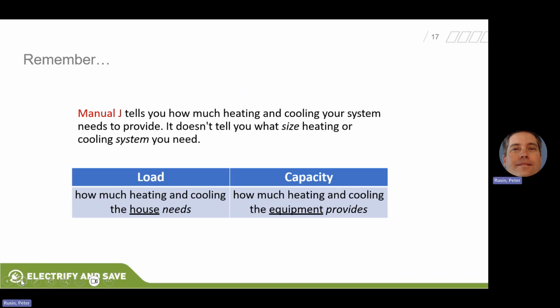One thing to remember is Manual J will tell you how much heating and cooling your system needs to provide, but it doesn't tell you the size of the heating equipment. If you remember in Module 1, we showed the differences in a 2-ton unit that vary widely after 47 degrees Fahrenheit. What we're working on today, and what this module is about, is making sure we understand how much heating and cooling the house needs. The capacity of the equipment comes in the next module.